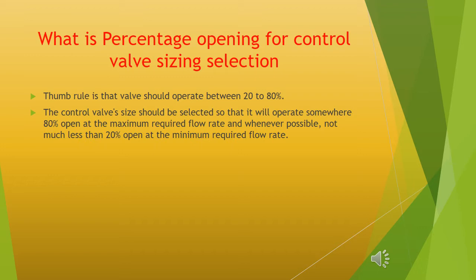What is the percentage opening for control valve sizing selection? The thumb rule is that a valve should operate between 20 to 80%. The control valve size should be selected so that it operates at approximately 80% open at the maximum required flow rate, and not much less than 20% open at the minimum required flow rate.